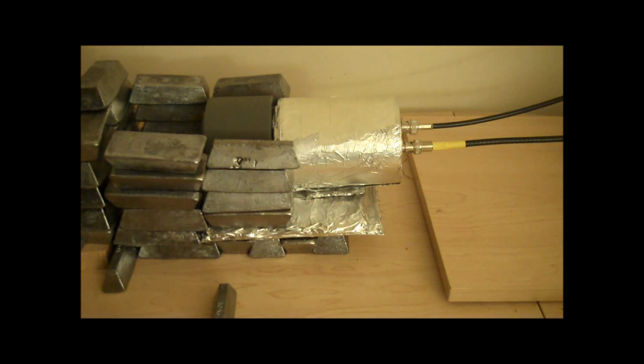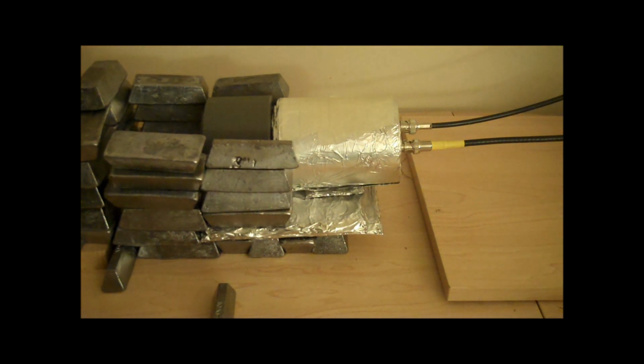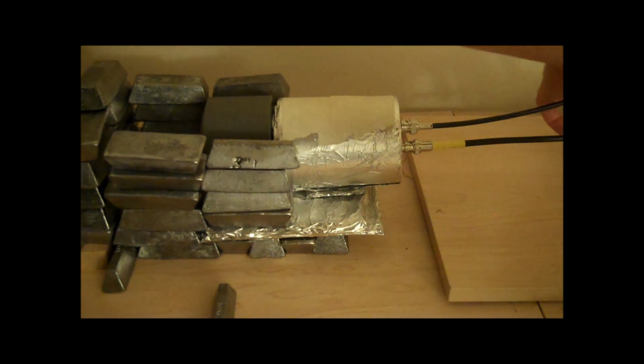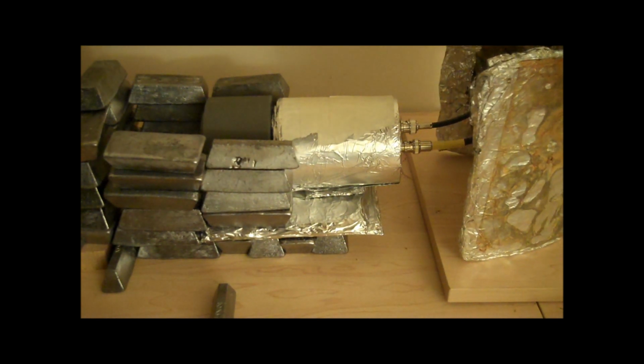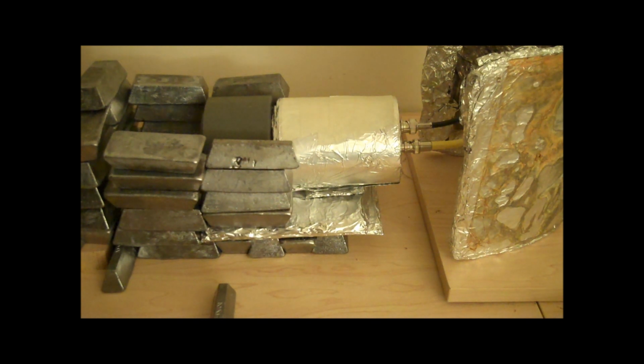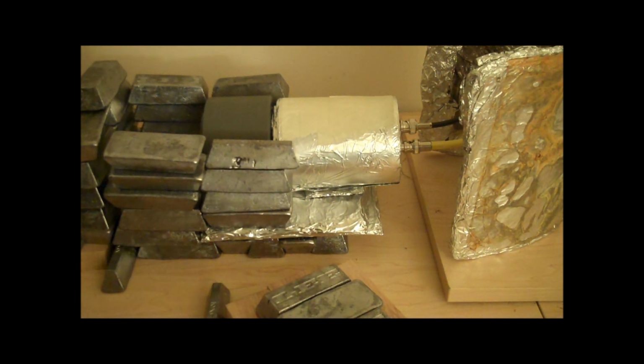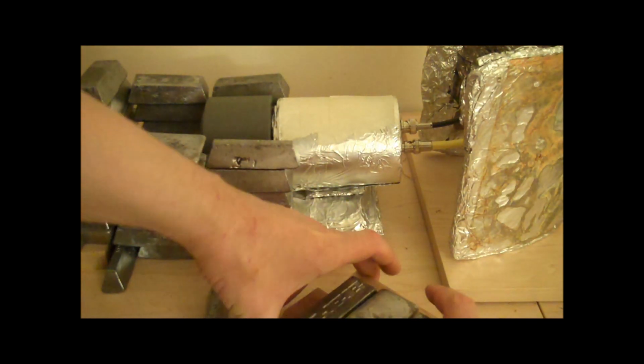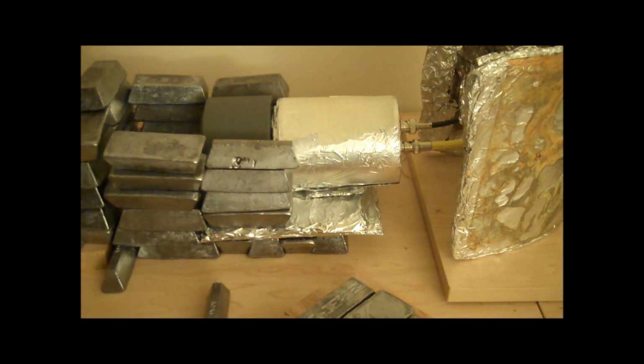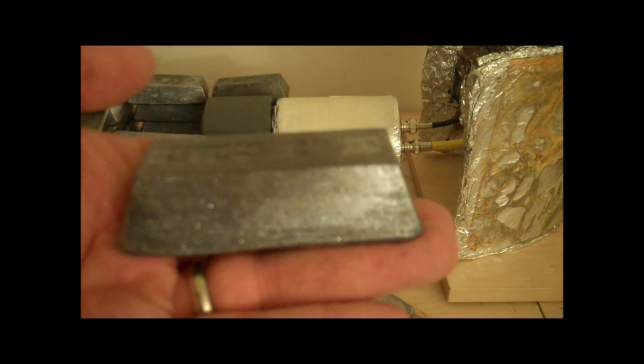Once the scintillation device has been set and is ready to go, let's put the protection on the back that guards the back. There is even a top piece right here. The top piece is made of blocks of lead supported by oak. Each one of these ingots is 3 inches long by 0.75 inches tall by about an inch in width.